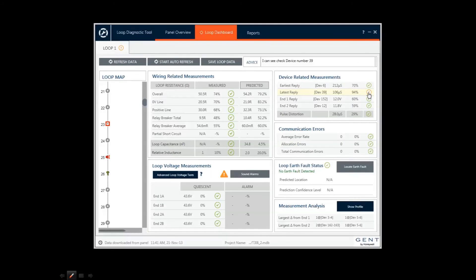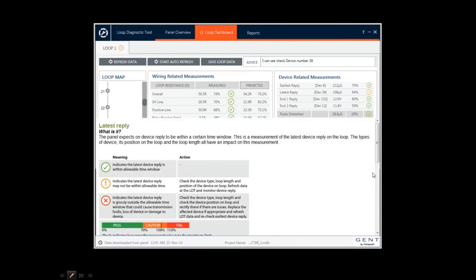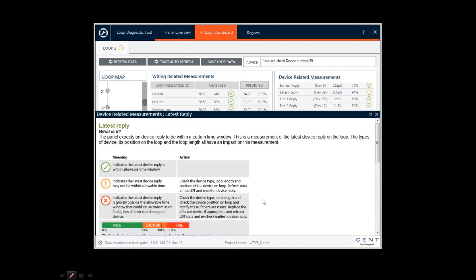If you click the exclamation mark, this reveals context-sensitive help. Here, this advises the engineer to refresh the loop reading and if the warning returns, there may be a problem with the device.